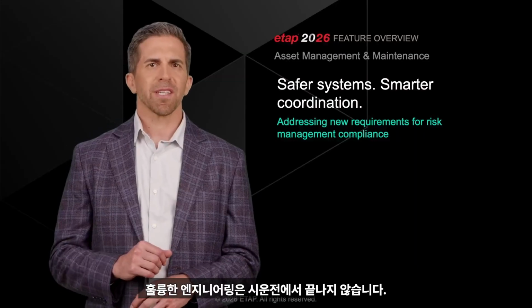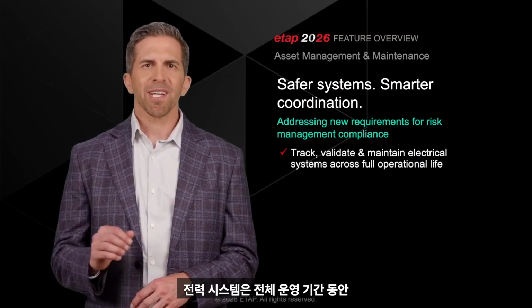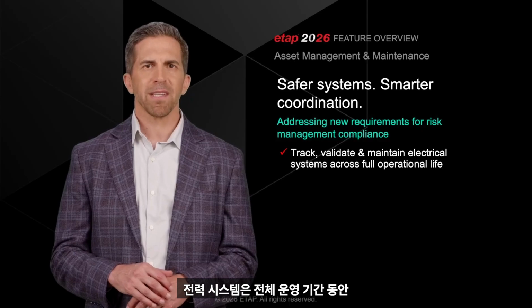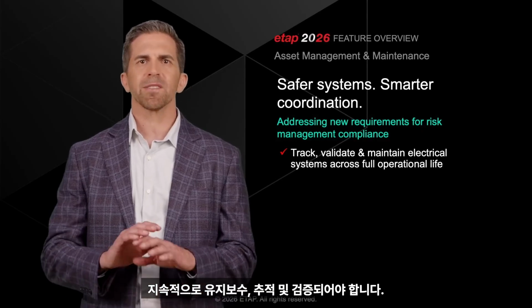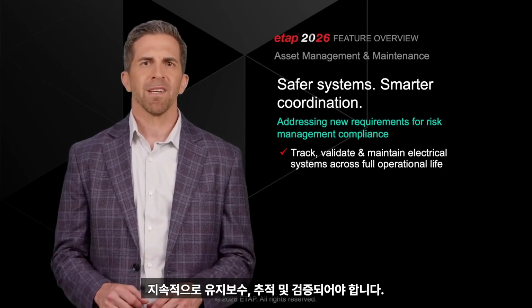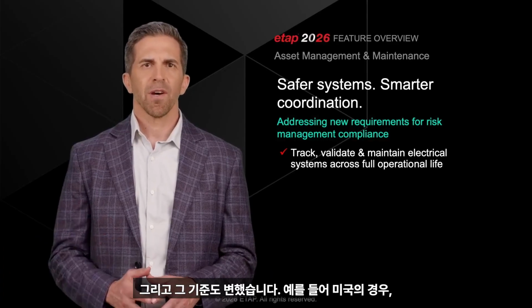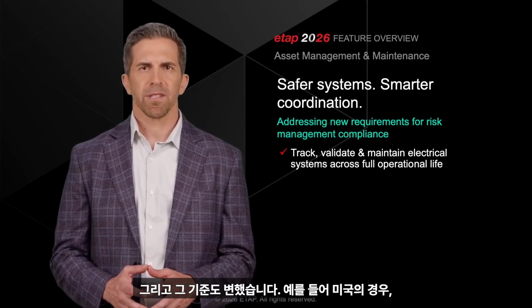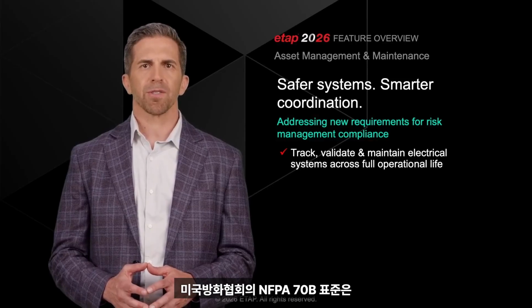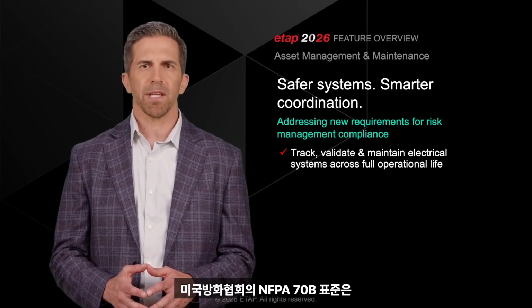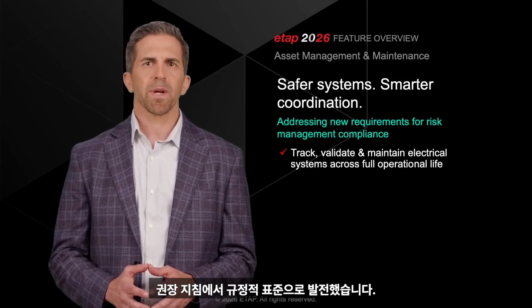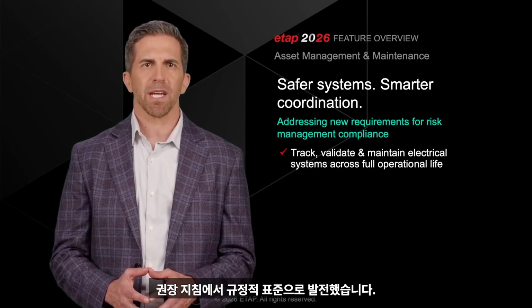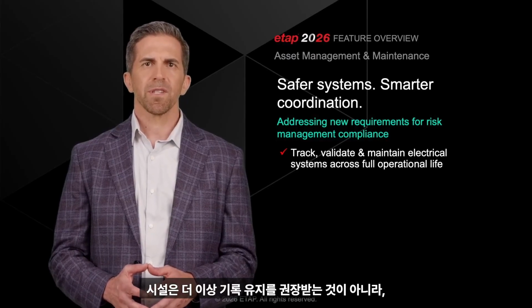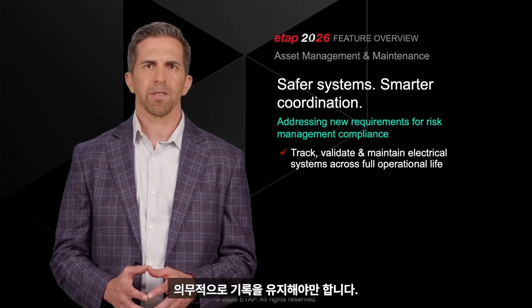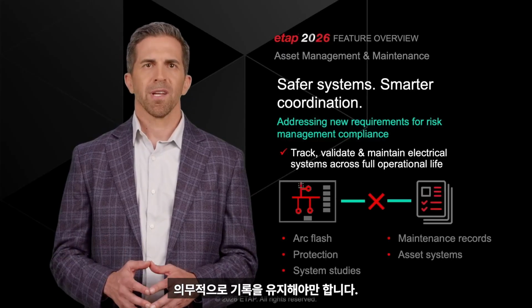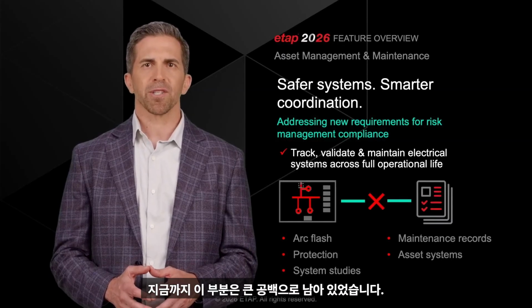Great engineering doesn't end at commissioning. An electrical system must be continuously maintained, tracked, and validated throughout its entire operational life. And the stakes have changed. For example, in the US, the National Fire Protection Association's NFPA 70B standard has evolved from a recommended practice to a prescriptive standard. Facilities are no longer encouraged to maintain records. They are required to. Until now, this has been a major gap.